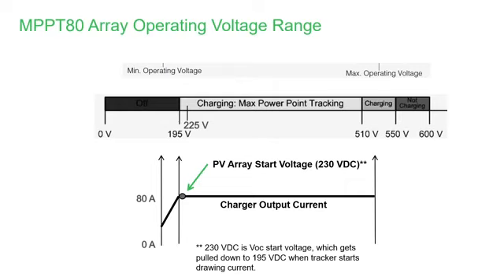Let me point out here, from 0 to 195 volts, this unit is simply going to be off, asleep. If you have less than 195 volts in the array, you will have 0 production. And this is also true on the upper range of the scale. From 550 to 600, you will have no charging, so that the unit can protect itself, because 600 volts is the maximum. So when you're string sizing, you want to make sure that you are in the middle of the range, so that you can cover most of the changes.